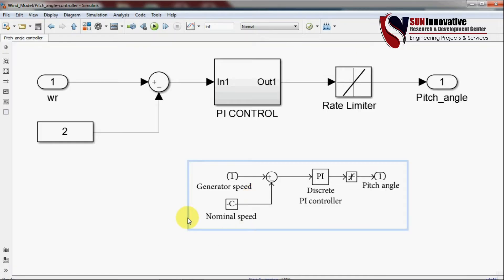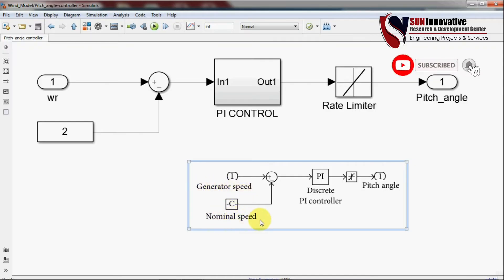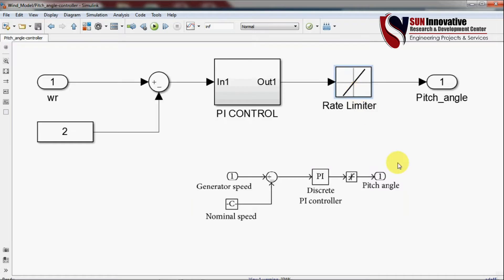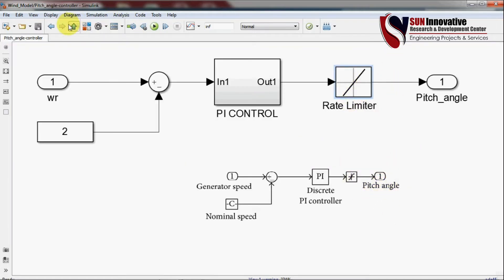For the pitch angle block: you have to find the generator speed and the nominal speed. Whatever error is generated is given to a discrete PI controller. There is also a rate limiter, and after this block you can easily find the pitch angle value.